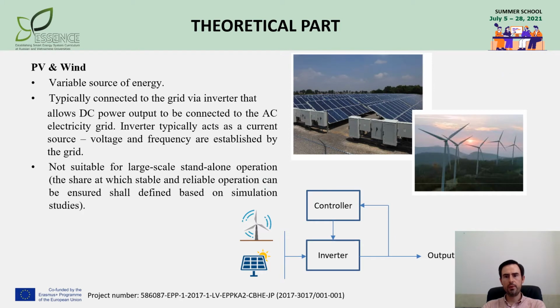The most popular today, PV and wind generators, have the following specifics. They have a stochastic, variable nature. Thus, accurate forecast technologies are required to ensure energy balance in microgrids. Otherwise, a strong connection with a utility of much larger size that may compensate renewable energy variation is necessary. Interconnection of renewable sources via grid-following inverters also changes the system dynamics and complicates parallel operation in case of grid faults. These two particularities limit the share of PV and wind generators and require additional studies to define the maximum penetration level.